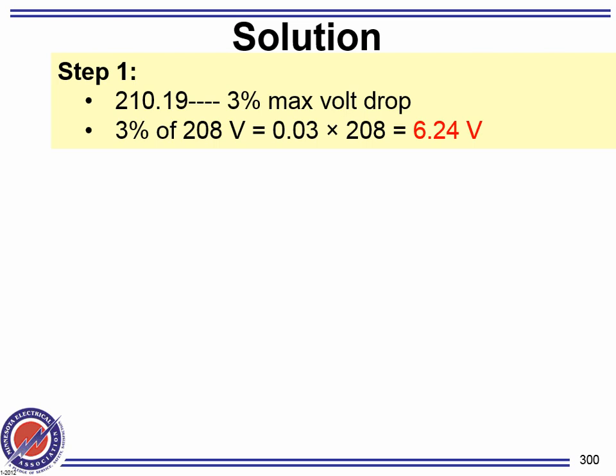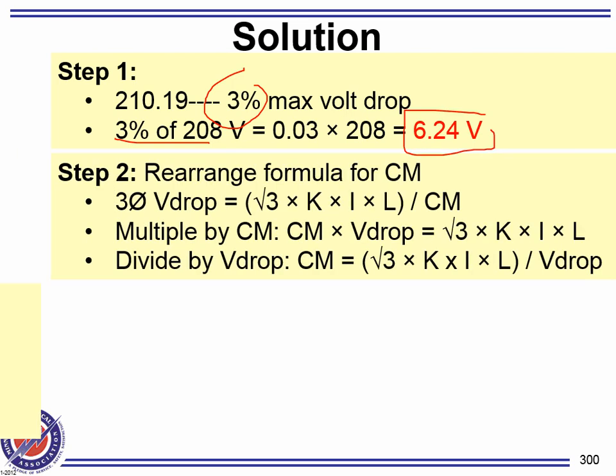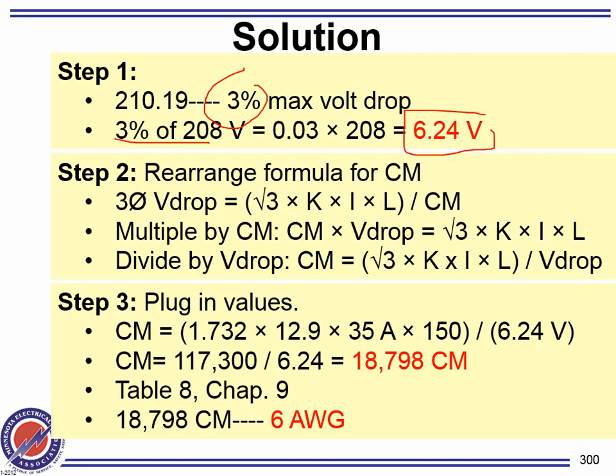Here's the 3% acceptable. Take 3% of 208. That'll get you how much you can lose. Then you need to drop. Then you flip the formula. Now here's a circular mil, gentlemen. Formula in the form of a circular mil. All right, so here's the 3-phase component. 12.9, that's K. Here's the amps. Here's the L, the distance.